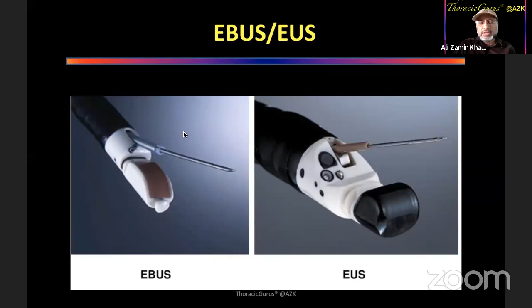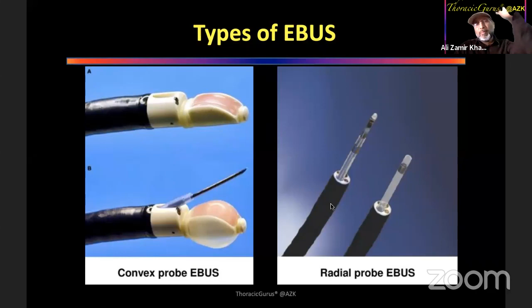So they have now come in with a new one, which is called a radial probe. The radial probe is a much thinner bronchoscope. It's a much thinner ultrasound mechanism. And the fiber that comes out, which carries the ultrasound, is at the tip of it. And it gives out ultrasonic image at the tip. This gives out at the side. This gives out at the tip. So you can actually manipulate this bronchoscope into the tertiary and the quaternary carina and take a biopsy from much, much deeper using the ultrasound. So this is how we do that.